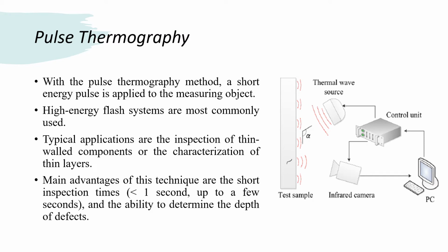First one is pulse thermography. With the pulse thermography method, a short energy pulse is applied to the measuring object. Here, high energy flash systems are the most commonly used.